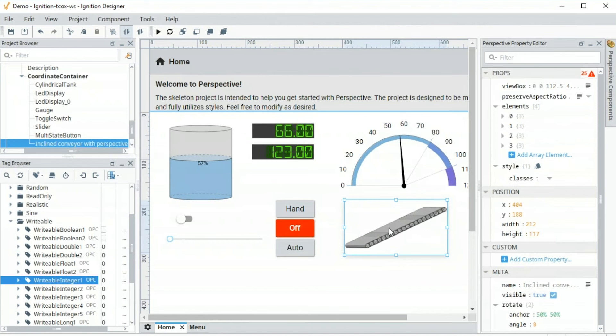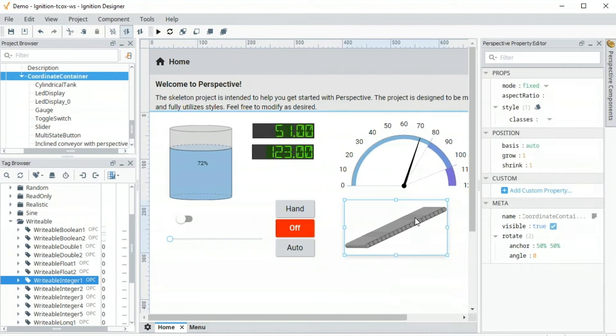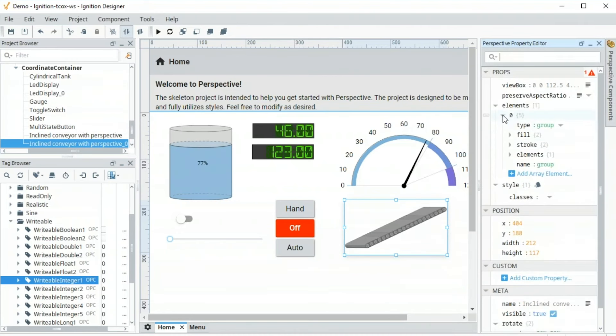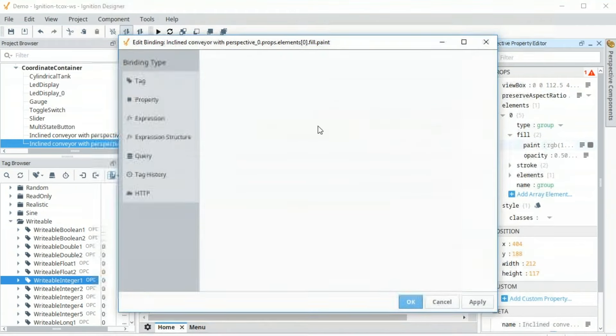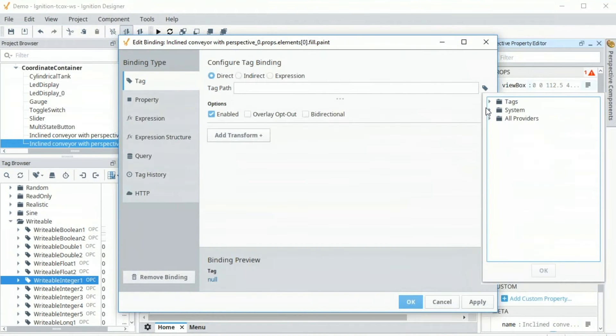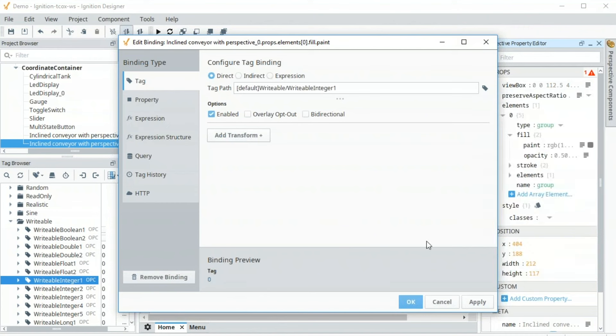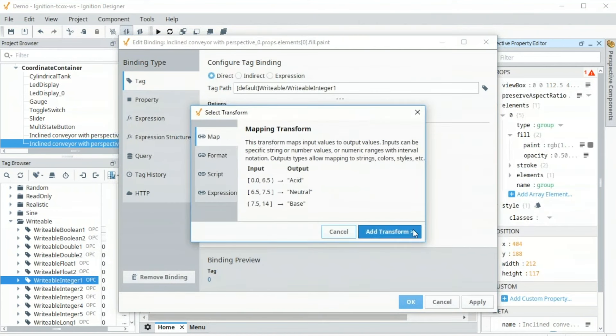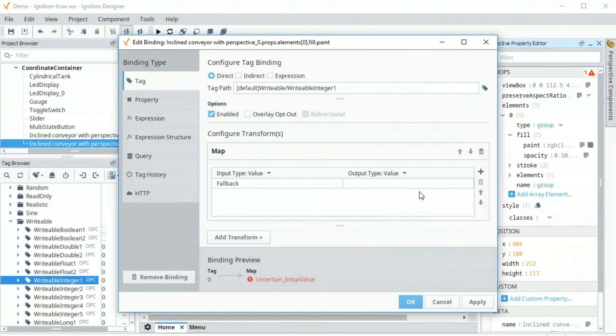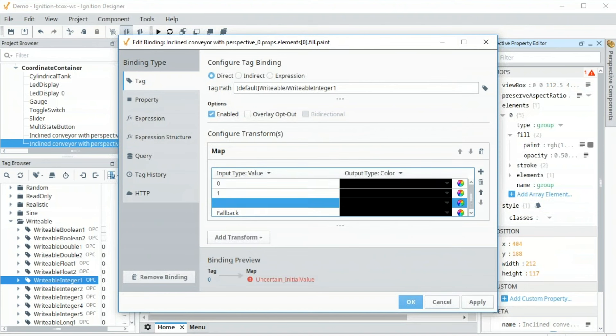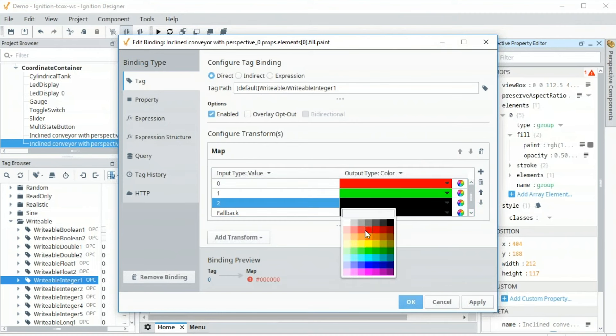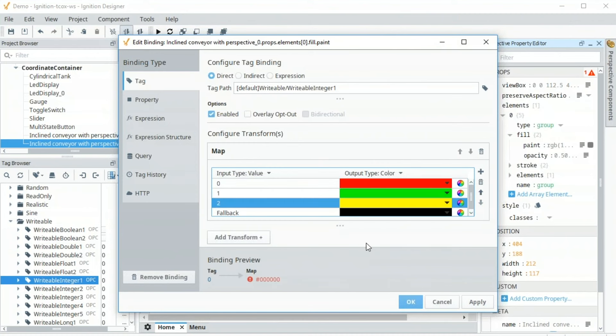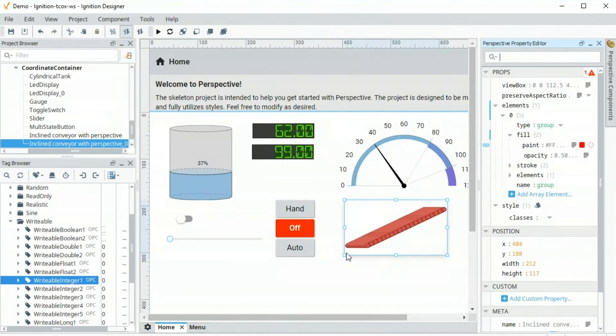Now, SVGs are comprised of a lot of different elements. We can stylize them individually or we can apply a tint on top. So let's flatten this object so we can have one object on top that we can do a tint. And it has a fill property, a paint. I'm going to bind that paint to a tag. We're going to select that writable integer 1 tag. And I want to go from a number to a color. So I'm going to add a transform or I'm going to do a mapping transform from a number to a color. So let's add three states there. 0, 1, 2. If it is 0, we'll make it red. If it is 1, we'll make it green. And if it is 2, we'll make it yellow. And that's it. I press OK. You can see that that tint is ready to go.